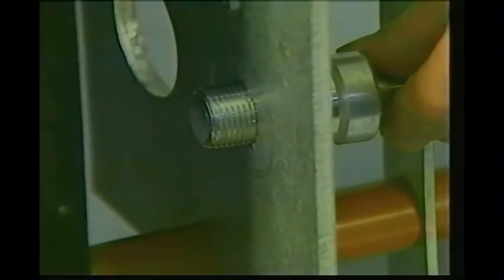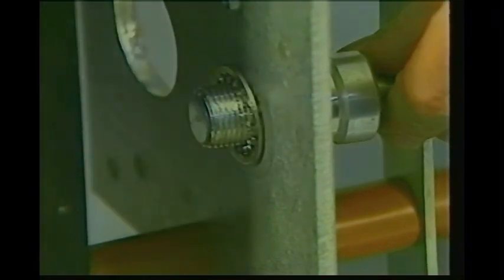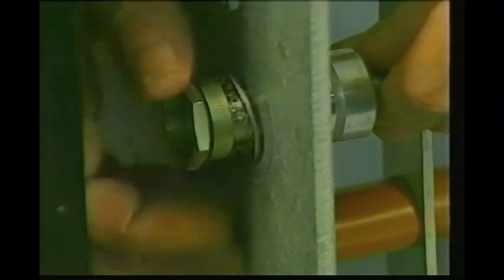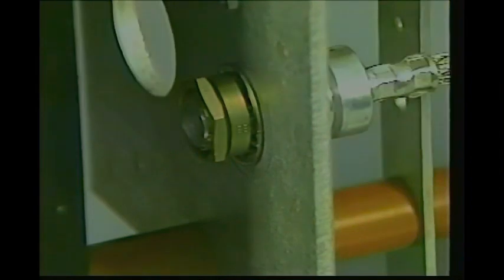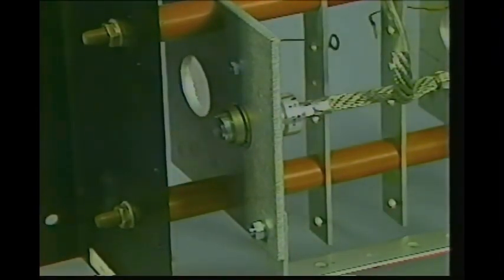Insert the diode, put the lock washer on, then put on the breakaway nut. Make sure that the round portion is against the heat sink plate. Tighten it finger tight. Then turn with a wrench until the hex portion breaks off.